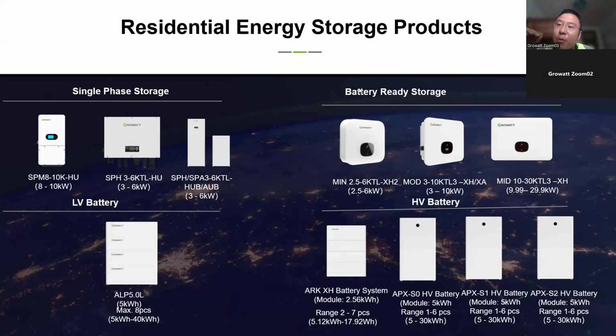The battery module we use for S0, S1, S2 are exactly the same — the same 5 kilowatt hour battery module. The only difference is the BDC box, the DC-DC booster, on top of it, which is different. For S0, the charge and discharge capacity is 5 kilowatt. S1 is 7.5 kilowatt charge and discharge, meaning for off-grid load 7.5 kilowatt, and S2 is 15 kilowatt. That's the only difference — just the charge and discharge capacity.